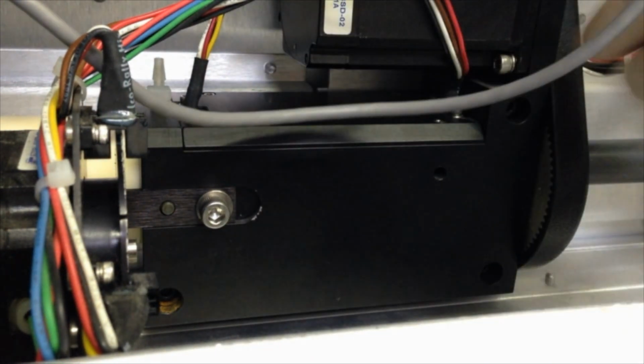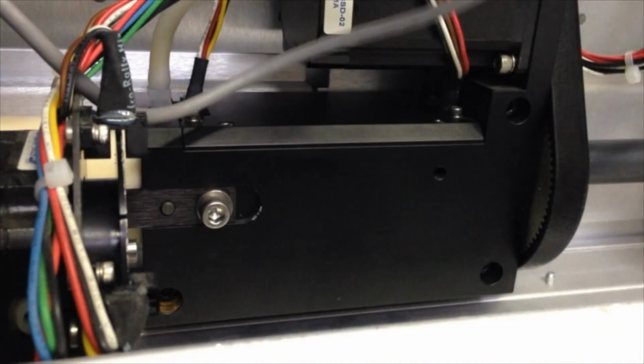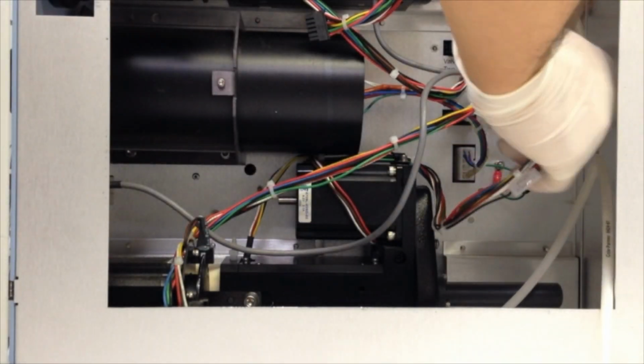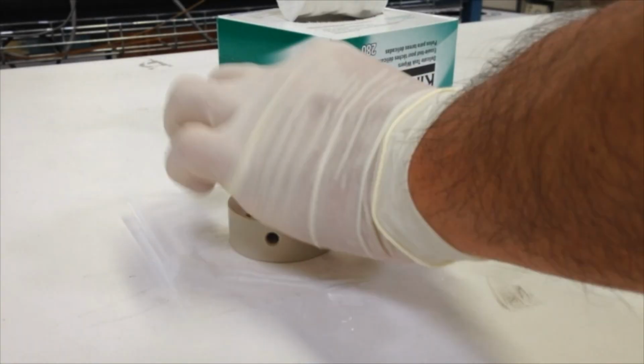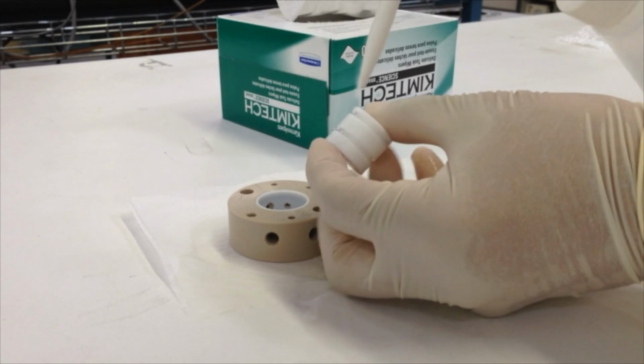Next, reconnect the piston wash tube to the piston wash connector. Plug in the pump wires to the control board. Rinse the valve with some methanol and wipe away any debris with a lint-free tissue.